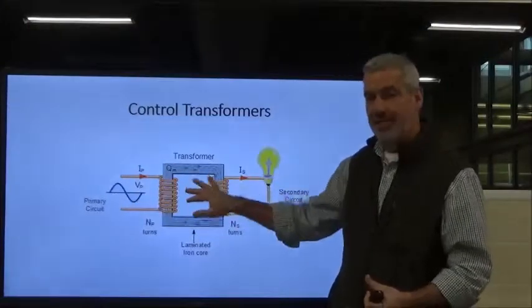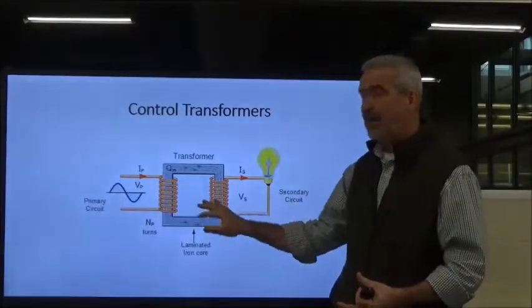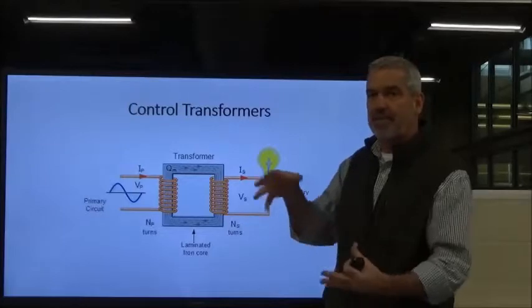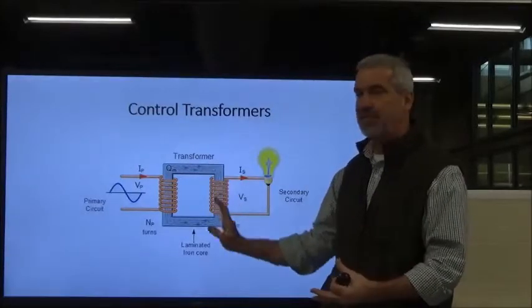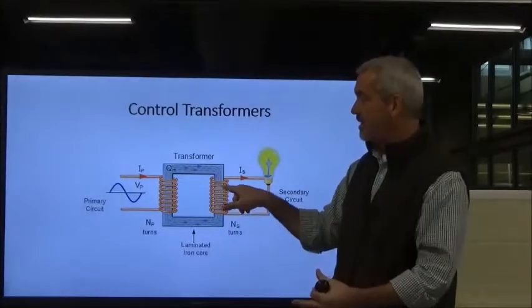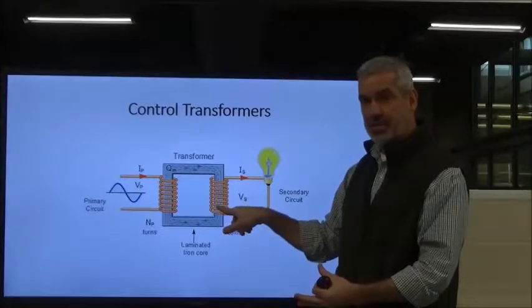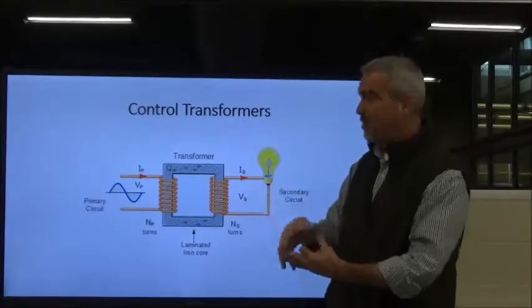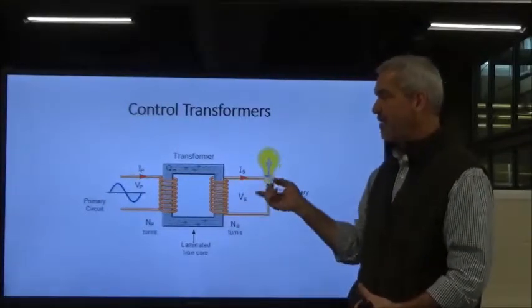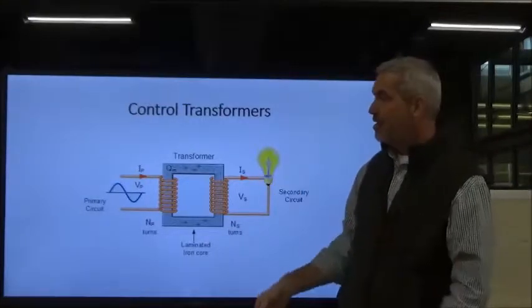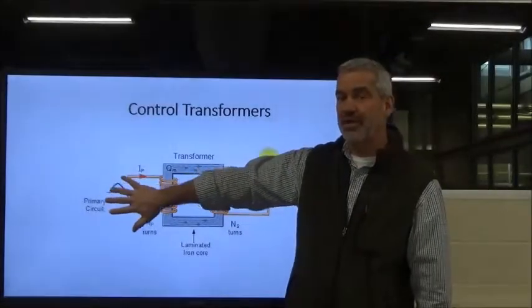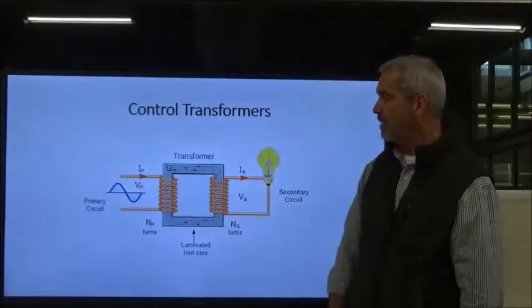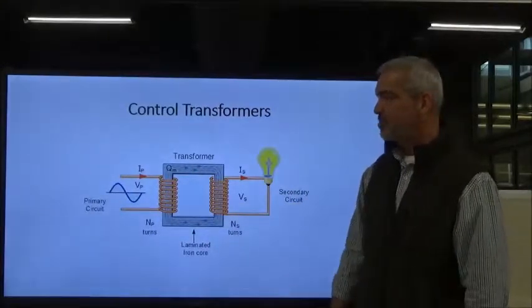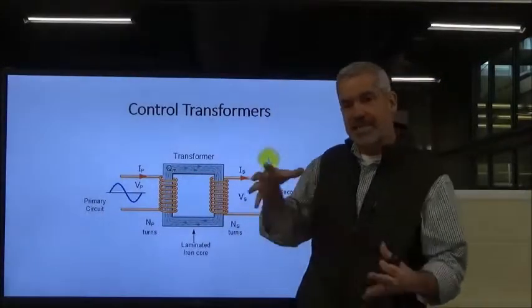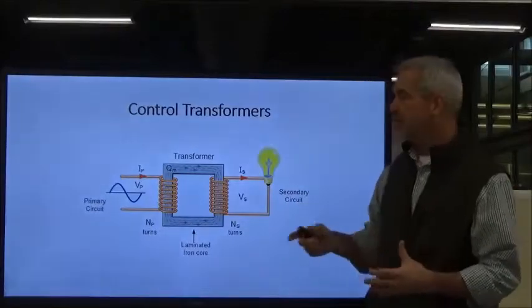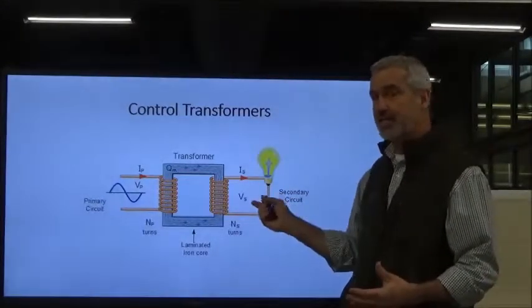Don't get me wrong, you'll have a heck of a magnet. But what you won't have is that alternating current building and collapsing, reversing direction back and forth inside this coil that's inducing the voltage. Without that, you won't have any voltage coming out of the secondary, no light or anything like that. So yeah, you can put DC voltage on there and watch it smoke in a heartbeat. That's why we have to have AC, alternating current—that's what causes us to have a voltage on the secondary side.